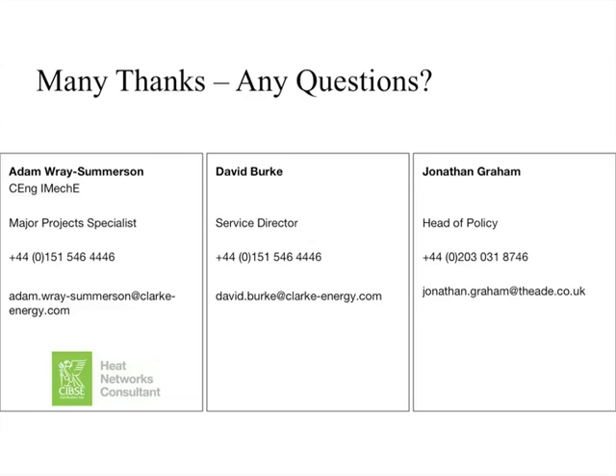As Jonathan was describing, we are under current changes right now to move to the medium combustion plant directive, which at 5% reference O2 level, the standard O2 level that most manufacturers refer their emissions to, we need to achieve an NOx emission of 250 milligrams NOx. All new Jenbacher engines, absolutely out of the box, will achieve the requirements of MCPD.